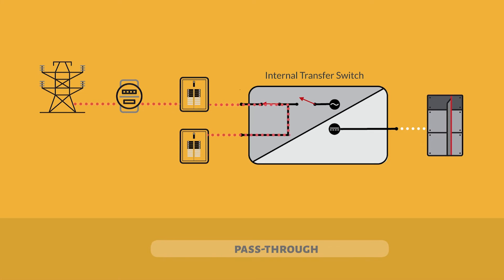While connected to the grid, the inverter is in a pass-through state, meaning taking the grid source and simply passing it through its relay contacts out to the protected loads panel. In this state the inverter does not modify the source. During a backup or inverting state, the AC input relay opens, isolating the grid from the hybrid inverter and preventing any backfeed while maintaining the output relay closed. This allows the inverted power from the batteries to power loads connected to the protected loads panel.